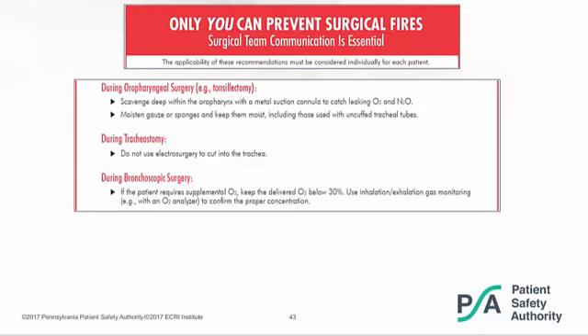During bronchoscopic surgery, I'll get back to tracheostomy in a minute. During bronchoscopic surgery, if the patient needs supplemental O2, then again, try to keep the concentration at or below 30%. Because what would typically catch fire inside the bronchus is the end of the bronchoscope, or you may get a flare-up of tissue that's being cauterized, and that flare-up in higher oxygen concentrations can again then ignite the end of the bronchoscope.